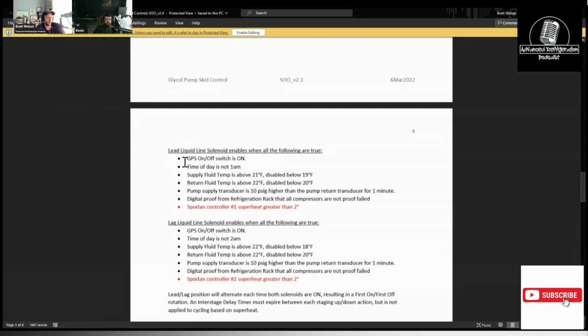We have no liquid line solenoids. Really? Just EEVs. You should. Nope. Unless they changed it. Now this is, I think, when it first came out. Because I think they were talking about doing that, and I didn't really like that because, God forbid, let's just say the power outage, but still, if the EEV is just running and chugging away because of a bad sensor, and it brings the temperature of that glycol all the way down to the floor, it should be able to enable it off, so we don't freeze anything up.